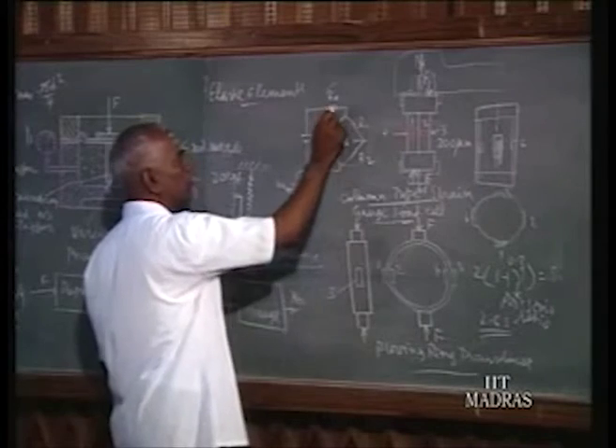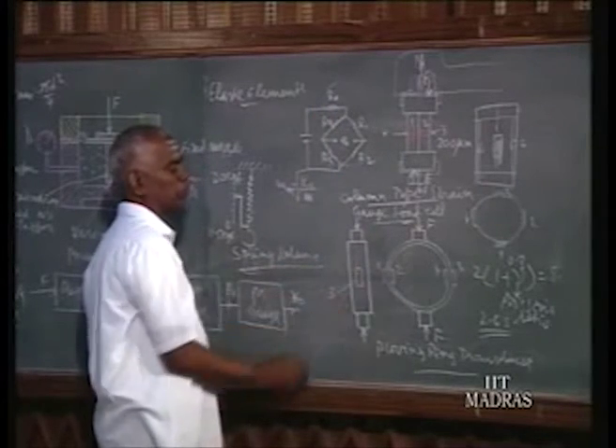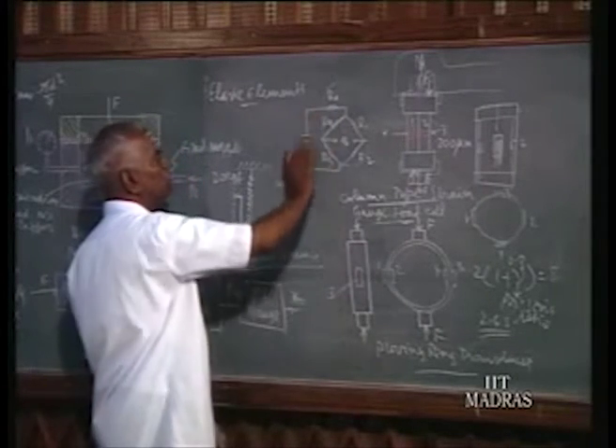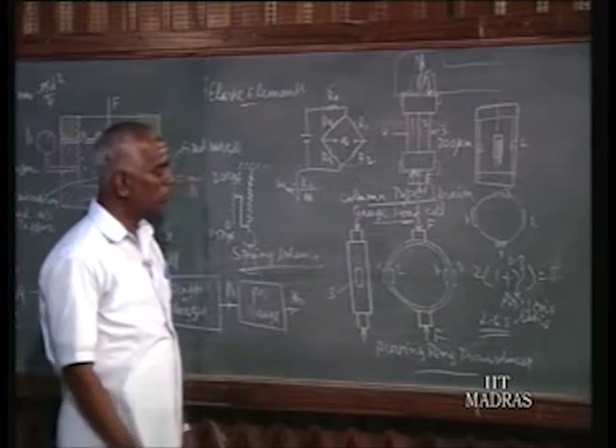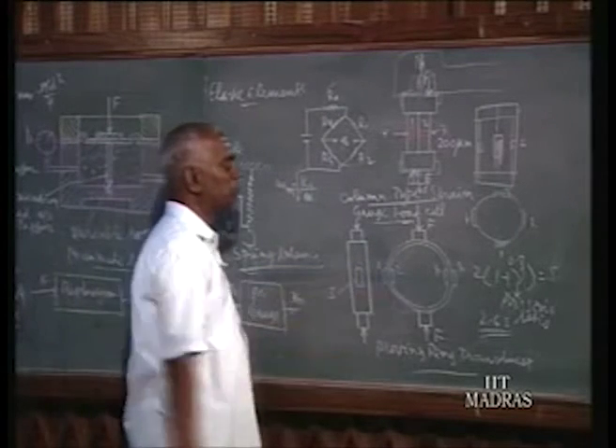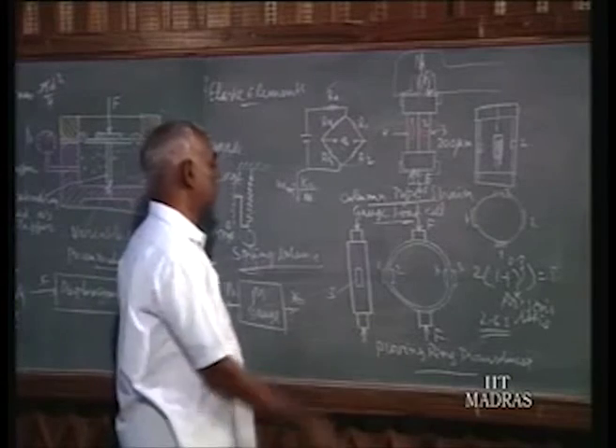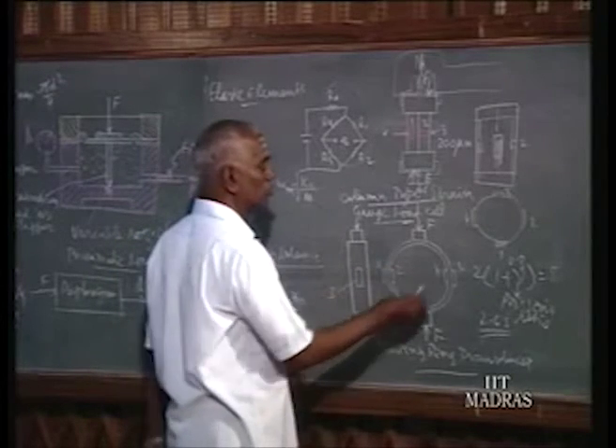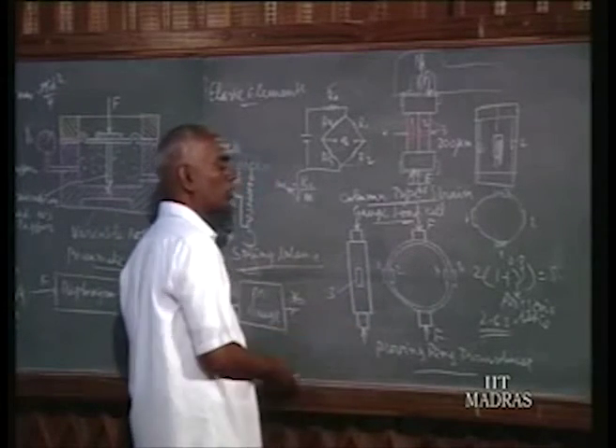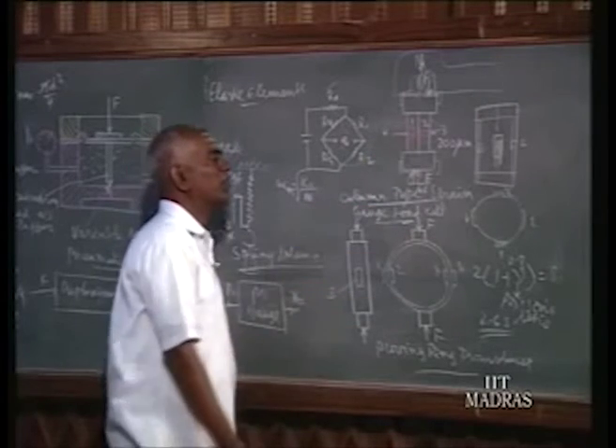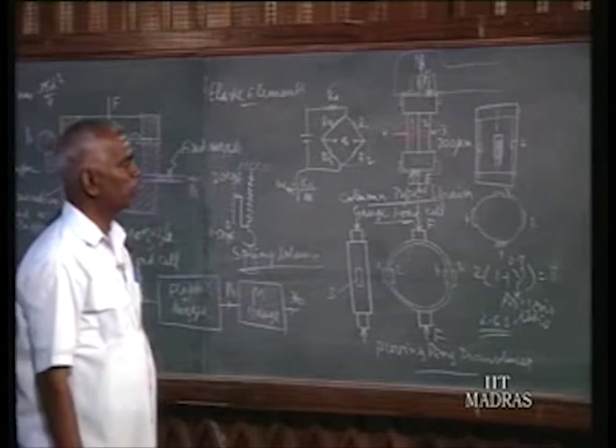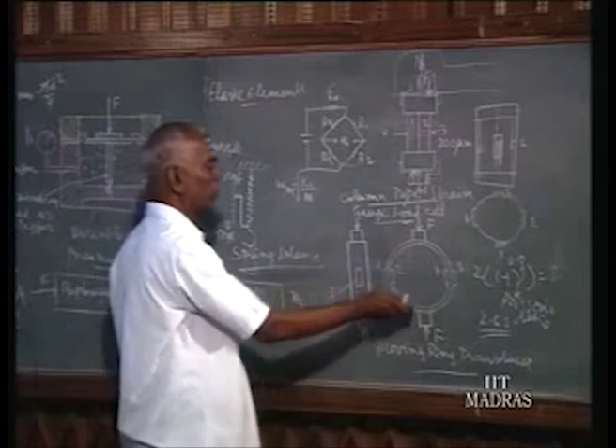Again you can have this compensation for elastic modulus change due to temperature. So the same circuit you can use for this, and the advantage is more sensitivity, but the load capacity is reduced. So probably 1 or 2 tons here, whereas for 50 or 100 tons we can go for the column type. Here it is a little bit reduced.